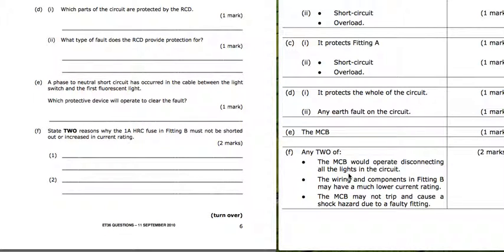So if we had a dead short across that 1 amp fuse in fitting B and there was a fault in that fitting, the MCB would operate and then all the lights would go out. The wiring and components in fitting B may have a much lower current rating. So if we short out that 1 amp fuse and 2 or 3 amps flows through it, we could damage the fitting. The MCB may not trip and cause a shock hazard due to a faulty wiring. So if we lose that protection in the fitting by shorting out this 1 amp HRC, then we could cause a problem within the fitting, and that could cause an electric shock.